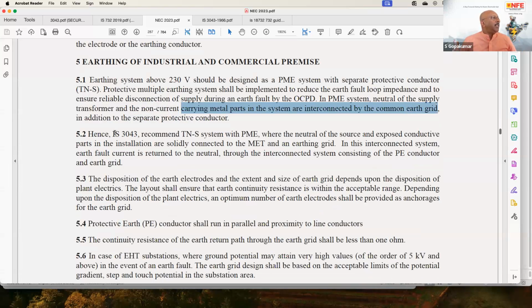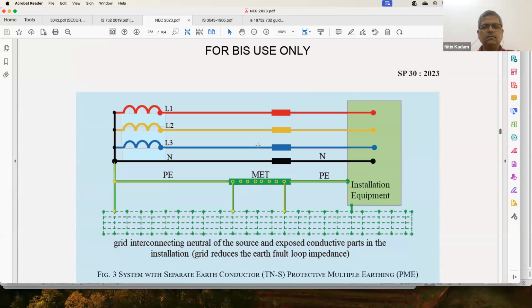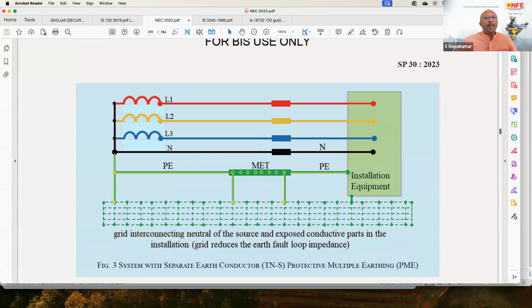You see here the second. Hence, IS 3043 recommends a TNS system with PME where the neutral of the source and exposed conductive parts in the installation are solidly connected to MET. And this picture is also given. For example, the installation equipment, the same picture which I have shown you, the installation equipment is connected to MET. Neutral of the transformer is connected to MET. Now, all these metal parts are also connected to the grid, interconnecting the neutral of the source and exposed conductive parts in the installation. The grid reduces the earth fault loop impedance. So for future buildings, this is the best method explained in the standard. Even if you have a little bit loose connections, you have an additional fault return path. So I hope that answers the question.